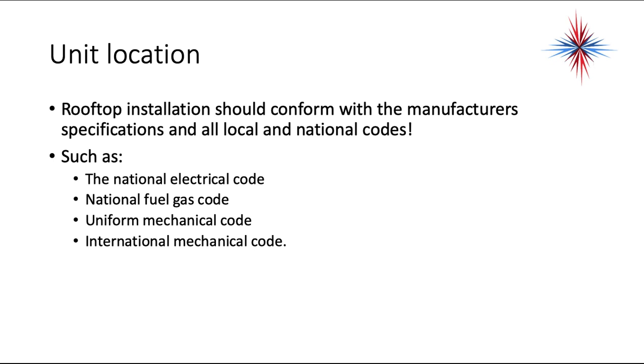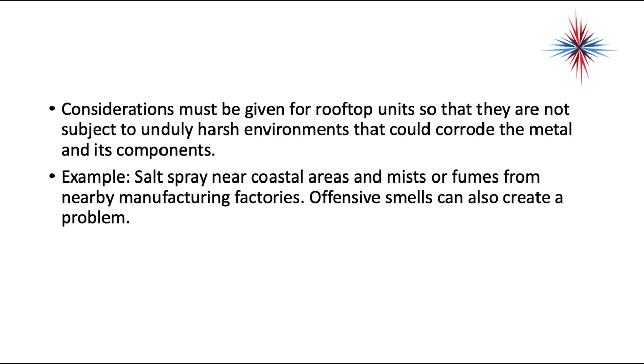You have to look at the National Electrical Code, National Fuel Gas Code, Uniform Mechanical Code, International Mechanical Code, and International Commercial Building Code or Residential Code. Consideration must be given for rooftop units so they are not subject to unduly harsh environments that can corrode the metal and its components. In some parts of the country, salt spray near coastal areas and mists or fumes from nearby manufacturing factories are a real problem.